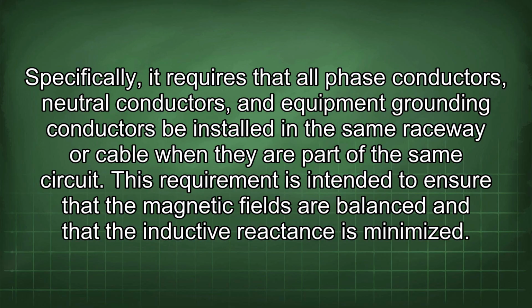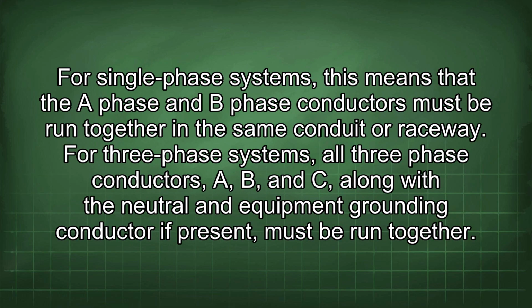Specifically, it requires that all phase conductors, neutral conductors, and equipment grounding conductors be installed in the same raceway or cable when they are part of the same circuit. This requirement is intended to ensure that the magnetic fields are balanced and that the inductive reactance is minimized. For single-phase systems, this means that the A-phase and B-phase conductors must be run together in the same conduit or raceway. For three-phase systems, all three-phase conductors A, B, and C, along with the neutral and equipment grounding conductor if present, must be run together.